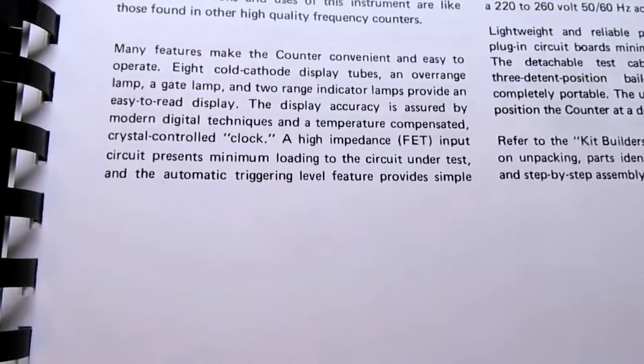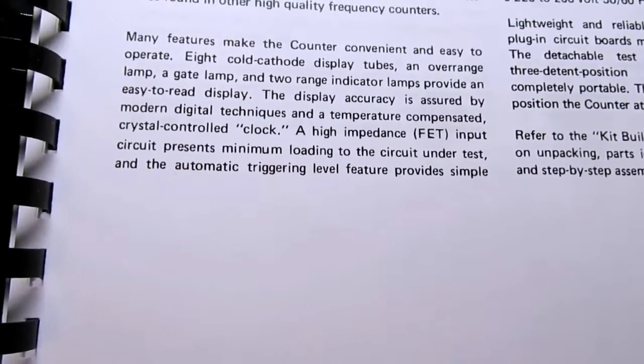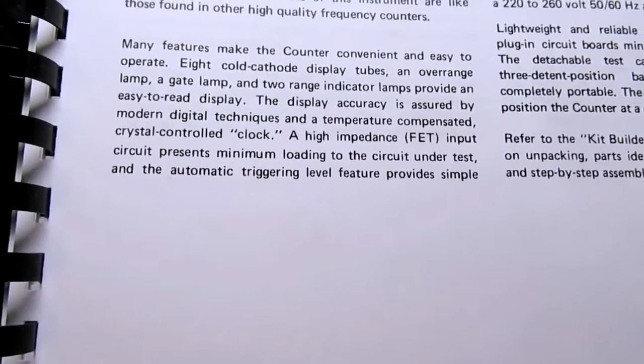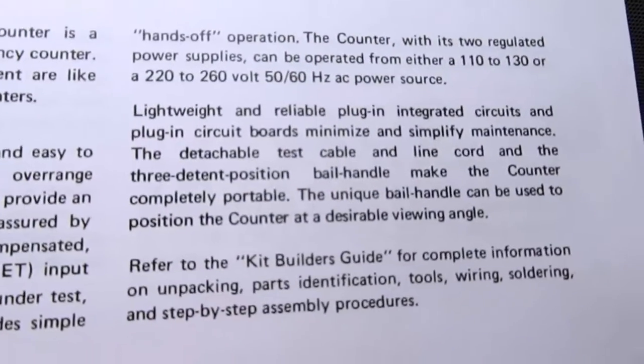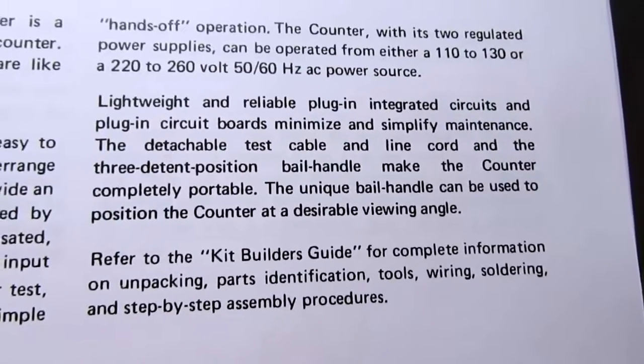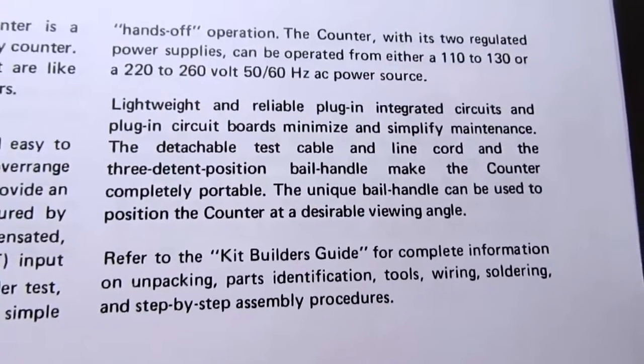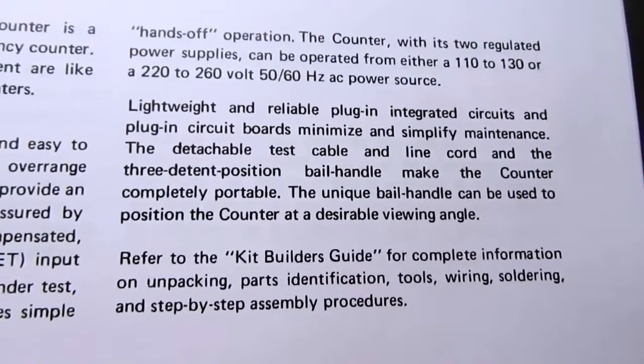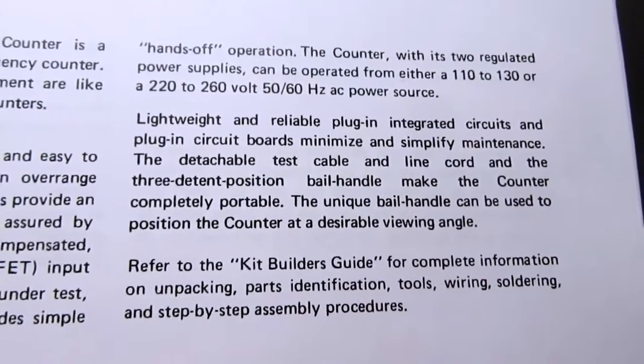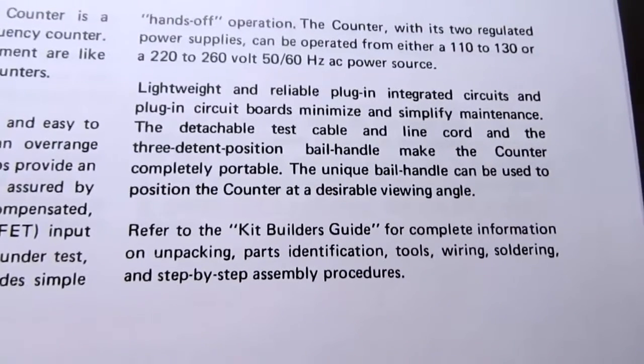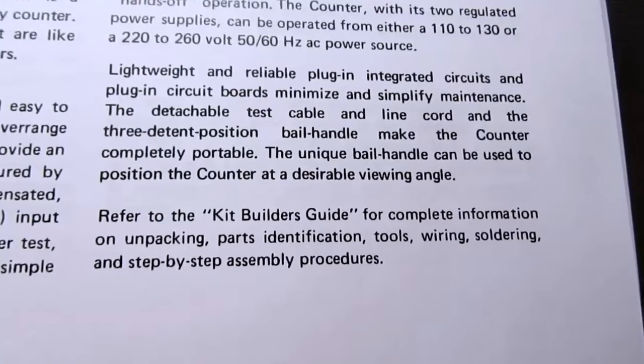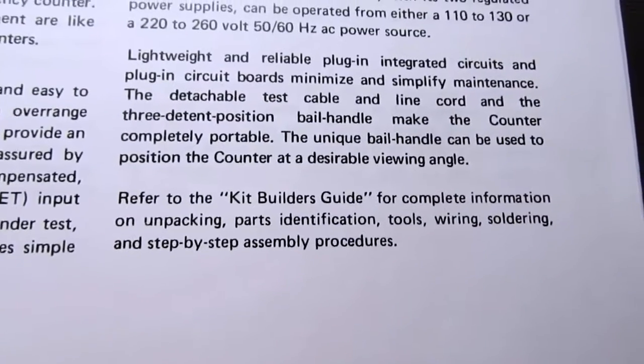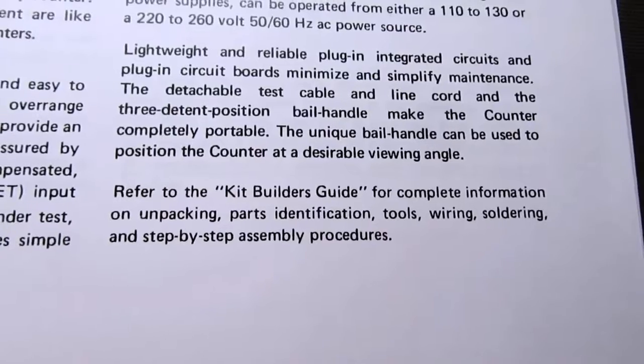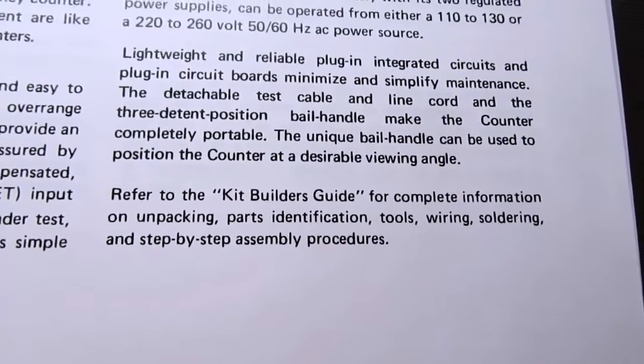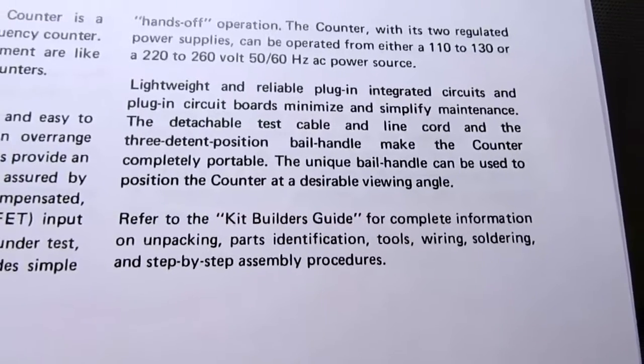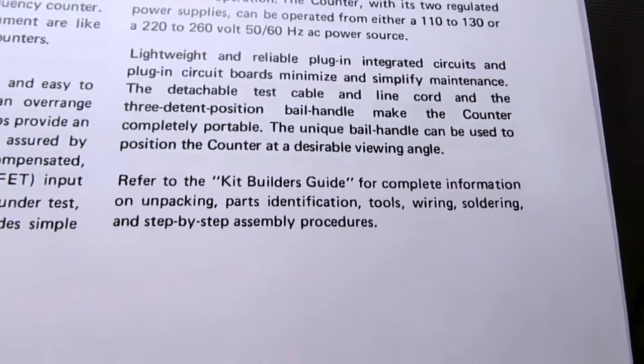A high impedance FET input circuit presents minimum loading to the circuit under test, and the automatic triggering level feature provides simple hands-off operation. The counter with its two regulated power supplies can be operated either from 110 to 130 or 220 to 260 volt 50-60 Hz AC power source. Lightweight and reliable plug-in integrated circuits and plug-in circuit boards minimize and simplify maintenance. The detachable test cable and line cord and the 3 detent position bail-handle make the counter completely portable. The unique bail handle can be used to position the counter at a desirable viewing angle.